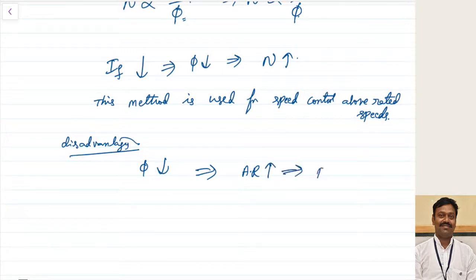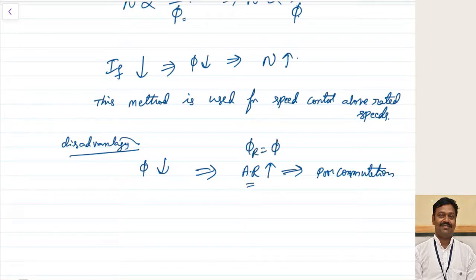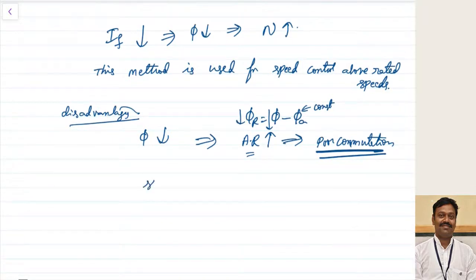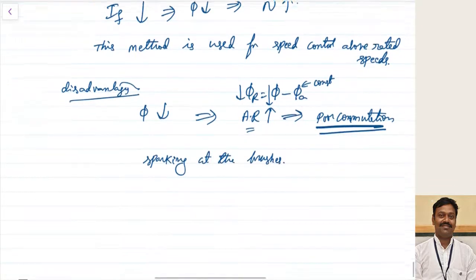This leads to poor commutation. The net resultant flux equals the main field flux minus the flux due to the armature. For a given load the armature flux is constant, so as the main field flux is decreased the resultant flux decreases, leading to poor commutation. Because of poor commutation, there will be sparking at the brushes. That is the only disadvantage of this technique.